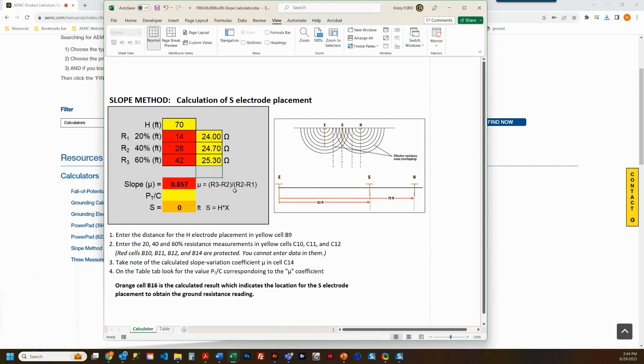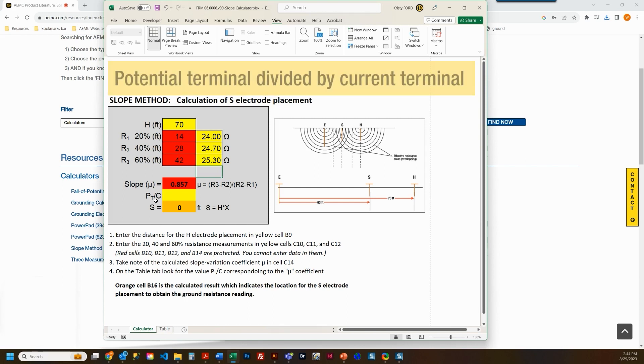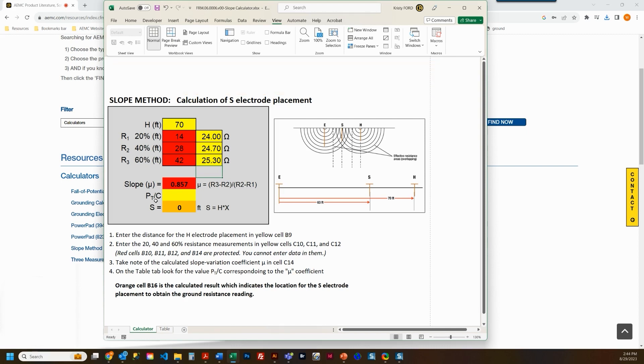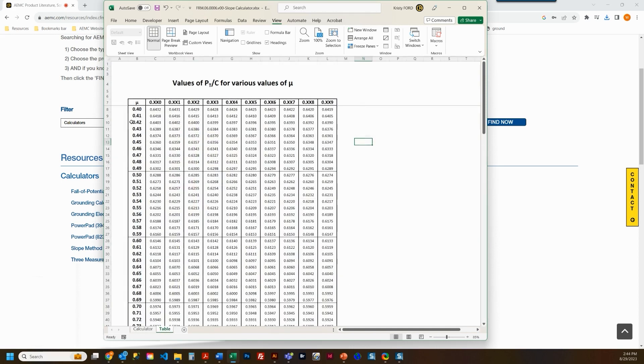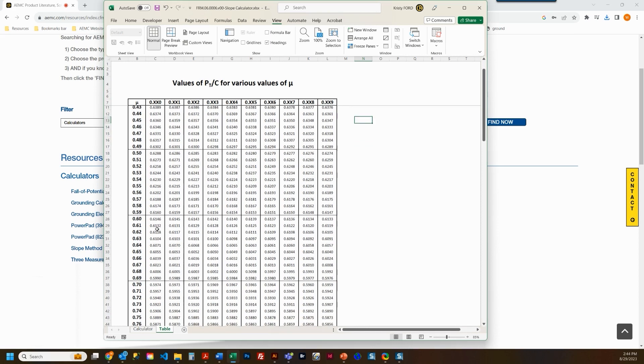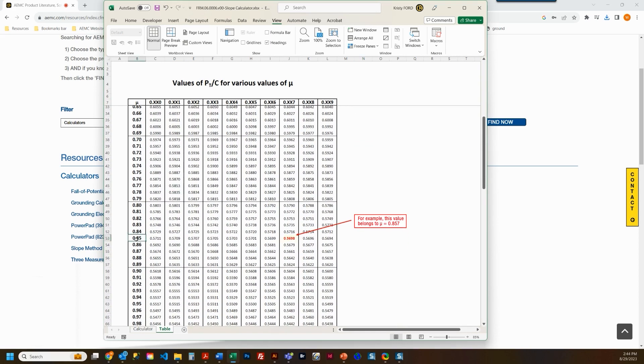This slope value will be used to determine the decimal multiplier, represented as Pt divided by C — potential terminal divided by current terminal — the value used to calculate the S electrode spacing. Next, select the table tab at the bottom of the sheet and locate the decimal multiplier for the potential electrode value for the calculated slope coefficient. This is a combination of the decimals under the coefficient column and the thousandth value, used to locate the correct coefficient value.